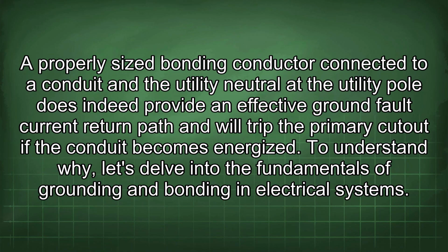A properly sized bonding conductor connected to a conduit and the utility neutral at the utility pole does indeed provide an effective ground fault current return path and will trip the primary cutout if the conduit becomes energized. To understand why, let's delve into the fundamentals of grounding and bonding in electrical systems.